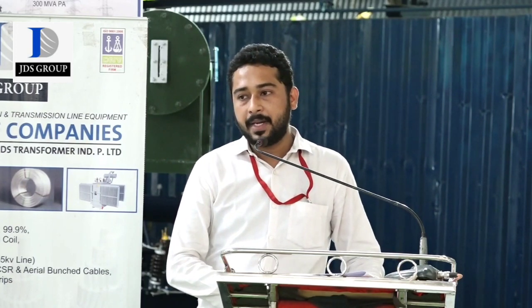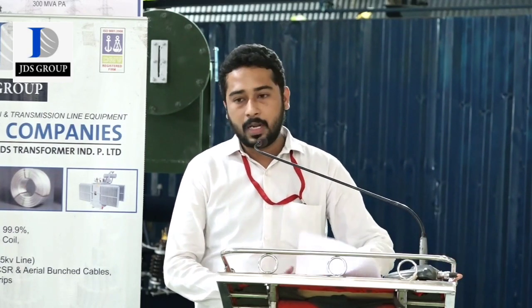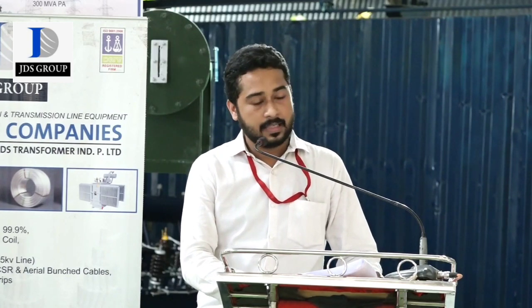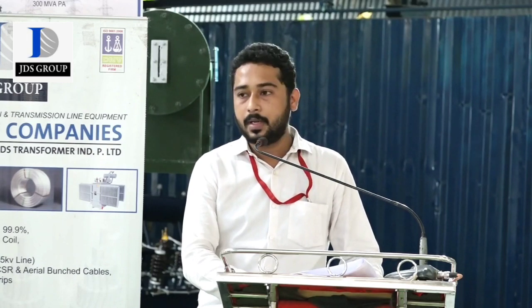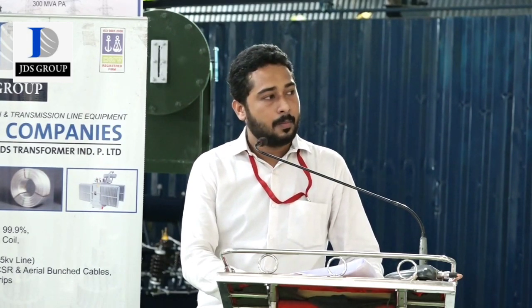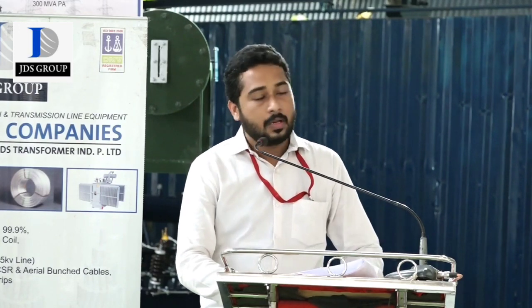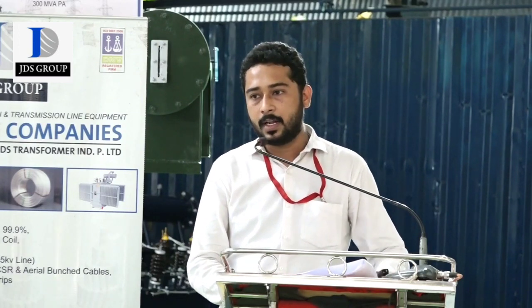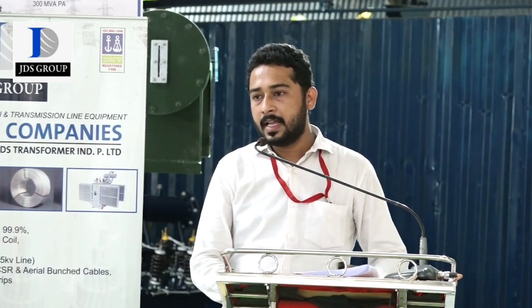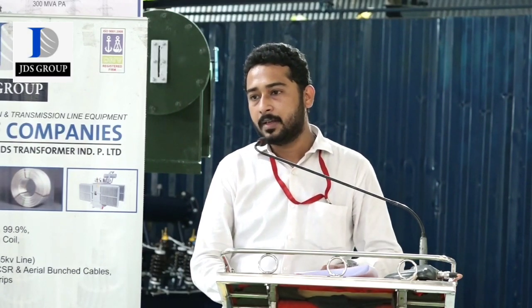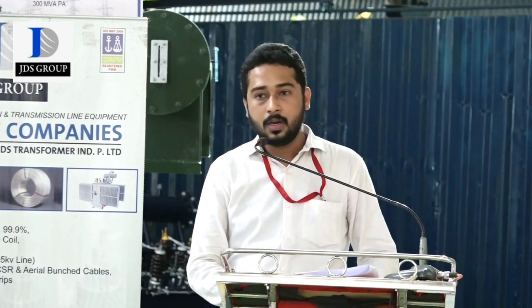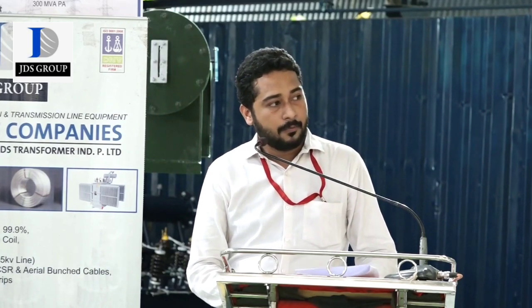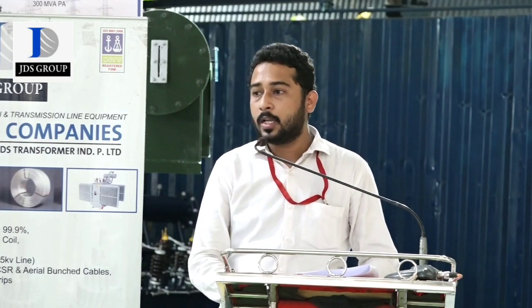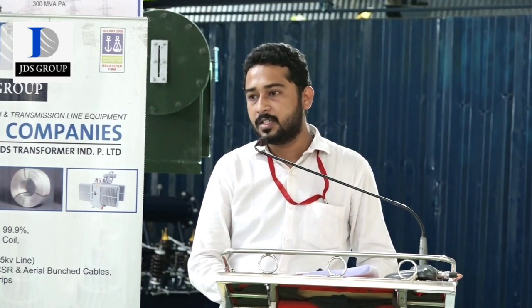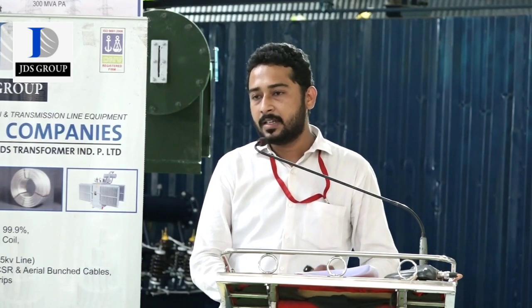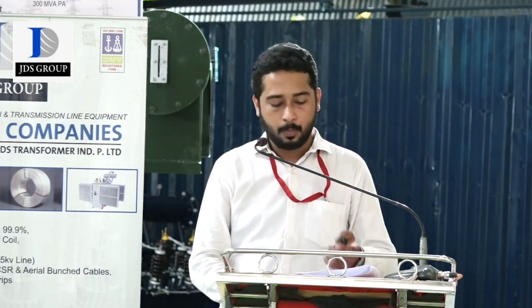Main features of our product, that is the cathode, are high surface area of contact, durability and reliability, corrosion resistance, excellent connectivity and conductivity, excellent and uniform current dissipation, less overall cost of ownership, pipe superiority and easy installation. If we consider the first, high surface area of contact, a plate has two surfaces, above and below, and all four sides. If we total the area, it comes to near about 7,20,000, but for the pipe it is about 11 lakhs. That means it is near about 1.6 times more than the plate when in contact with soil, so ultimately the dissipation in earth is more with the pipe as compared to the plate.